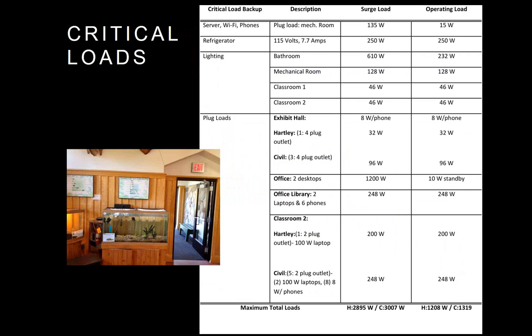It turns out, in reality, this is something we found out as we moved forward with the project: when you're doing a retrofit, you bring in the master electrician and find out what things are hooked up together. You don't always get to simply pick which rooms or outlets you want supported, because of how the wiring is done. In the end, we had more on these critical loads than we anticipated and had to go back and cut some out. That was unforeseen, and a real learning exercise for both of us.